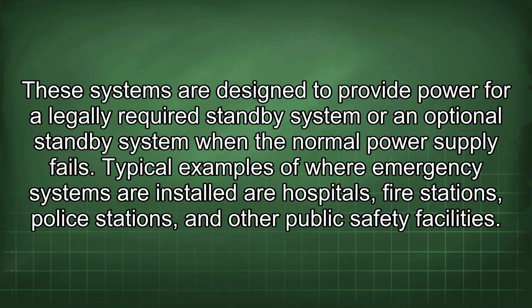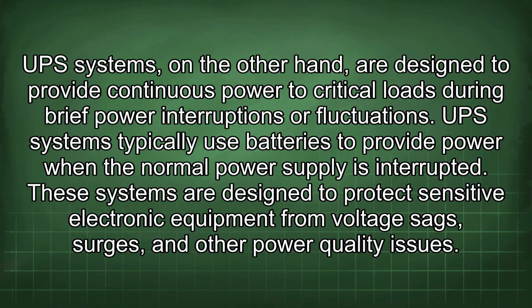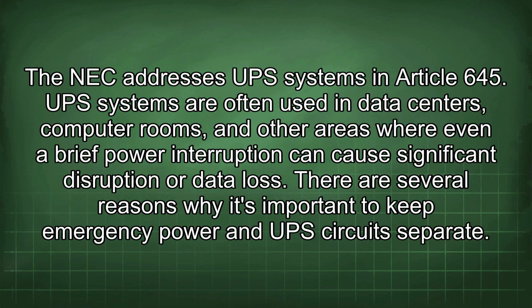These systems are designed to provide power for a legally required standby system or an optional standby system when the normal power supply fails. Typical examples of where emergency systems are installed are hospitals, fire stations, police stations, and other public safety facilities. UPS systems, on the other hand, are designed to provide continuous power to critical loads during brief power interruptions or fluctuations. UPS systems typically use batteries to provide power when the normal power supply is interrupted. These systems are designed to protect sensitive electronic equipment from voltage sags, surges, and other power quality issues. The NEC addresses UPS systems in Article 645. UPS systems are often used in data centers, computer rooms, and other areas where even a brief power interruption can cause significant disruption or data loss.